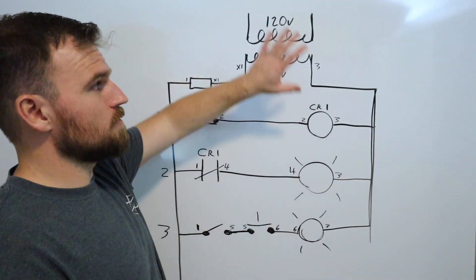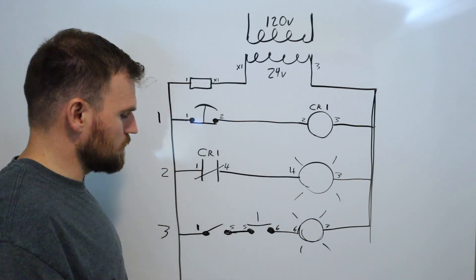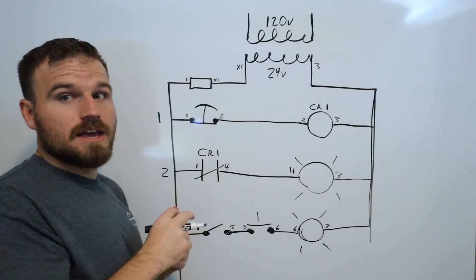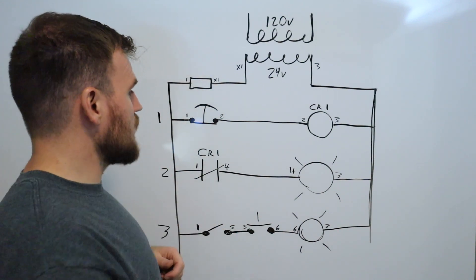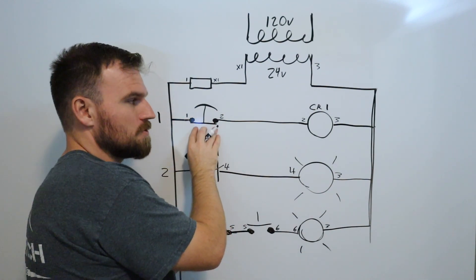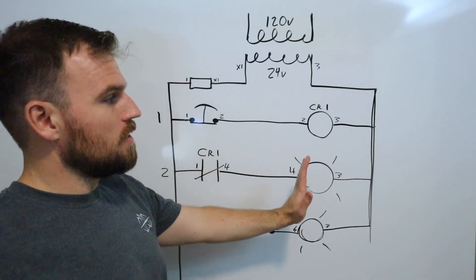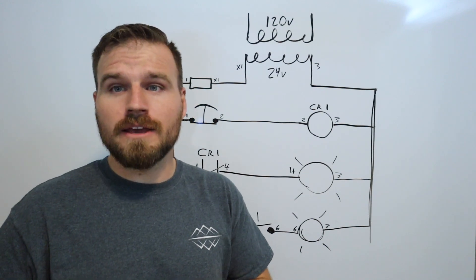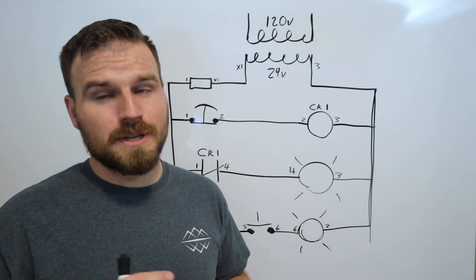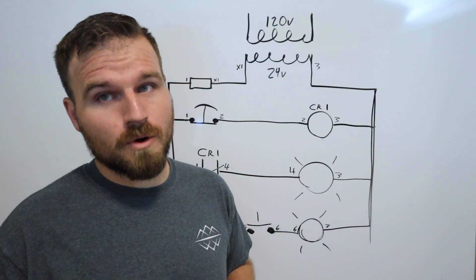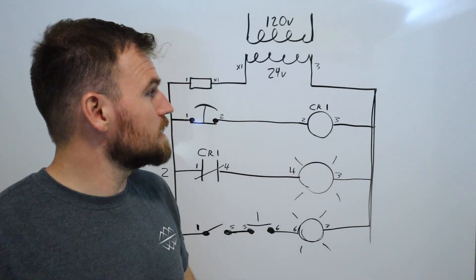To summarize: transformers go at the top, the breaker comes next, and the X1 terminal keeps wire number one constant throughout the hot side - even across multiple pages. Every time the wire passes through a component, the wire number changes. Everything on the hot side is red; the return is always white. Wire labels should be placed within about a quarter inch of where the wire connects to the component. Make sure wire colors are correct before moving forward.